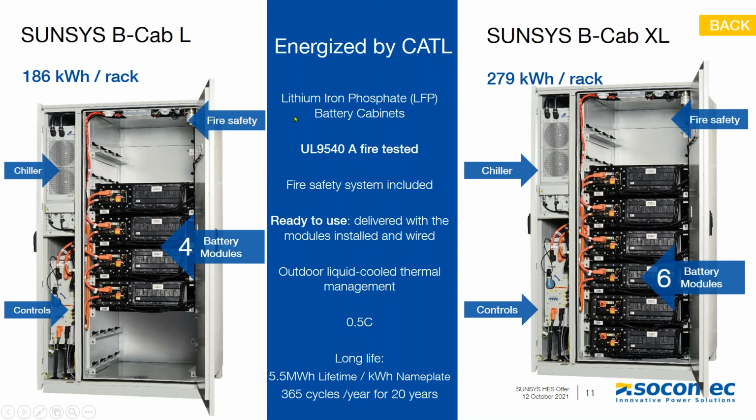The second thing is, while lithium iron phosphate batteries are inherently a safer battery, what you really want to hang your hat on is that they have a very good result on the large scale fire test. So the fire test here is the full battery cabinet, actually two of them, one next to the other, electrically and thermally tortured until a runaway is initiated. And then the test is what happens in the next 2 hours. And for these, it's pretty uneventful. It just slowly cools off. So it's a very thermally stable battery system.